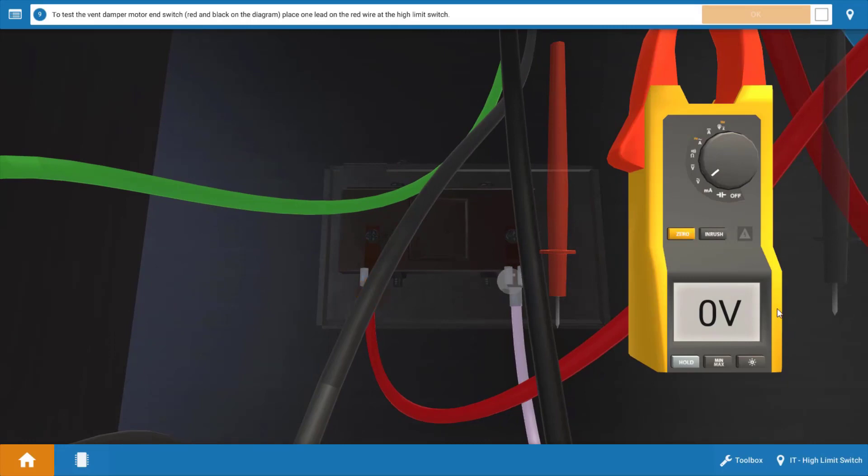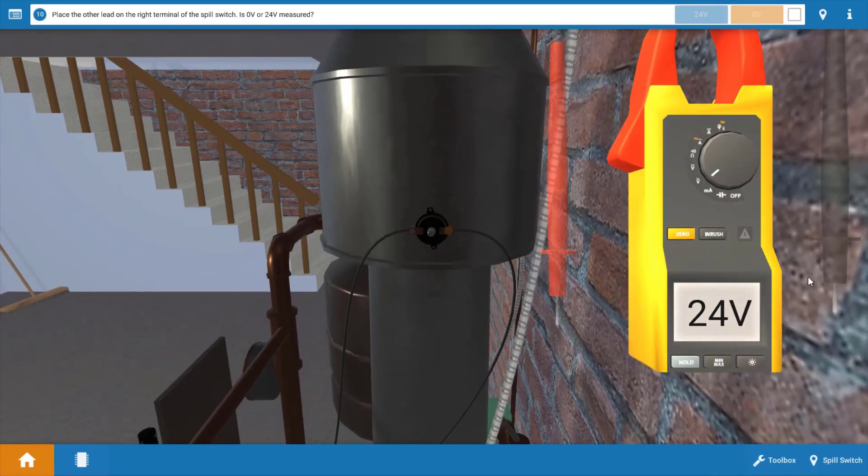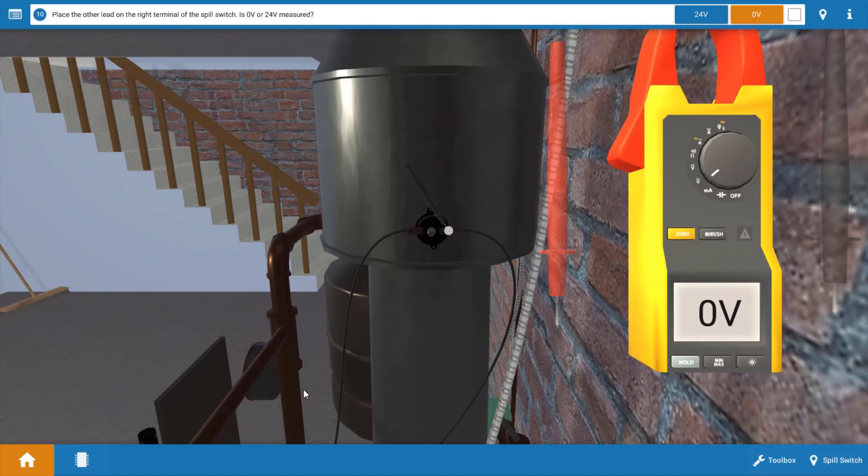We measured zero volts at the gas valve. Next, we're going to place one of the leads on the red connection at the high limit switch. Click OK. Once we've done that, we're going to place the other lead on the spill switch at the right side here on that orange glowing hot spot. Now if you're a little confused on this, let's go back to the wiring diagram.